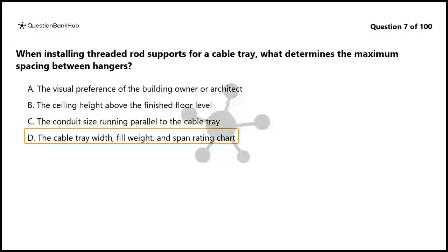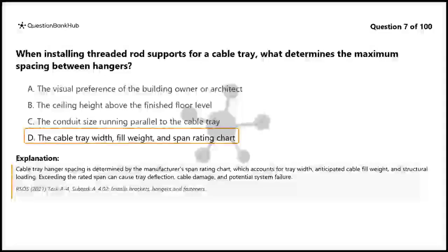The correct answer is D. The cable tray width, fill weight, and span rating chart. Cable tray hanger spacing is determined by the manufacturer's span rating chart, which accounts for tray width, anticipated cable fill weight, and structural loading. Exceeding the rated span can cause tray deflection, cable damage, and potential system failure.